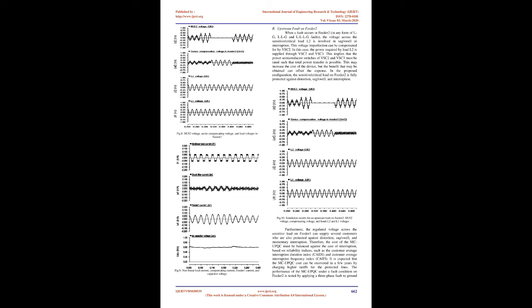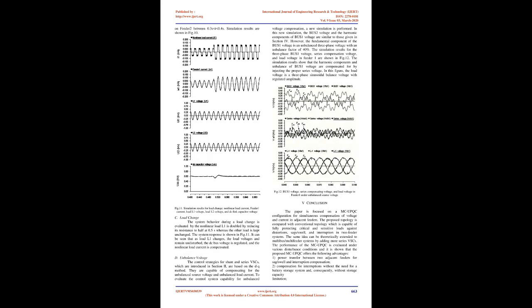Let us consider that the power system in Fig. 2 consists of two 3-phase 3-wire 380 V RMS line-to-line, 50 Hz utilities. The bus 1 voltage, UT1, contains the 7th order harmonic with a value of 22%, and the bus 2 voltage, UT2, contains the 5th order harmonic with a value of 35%. The bus 1 voltage contains 25% sag between 0.1 s and 0.2 s and 20% swell between 0.2 s and 0.3 s. The bus 2 voltage contains 35% sag between 0.15 s and 0.25 s and 30% swell between 0.25 s and 0.35 s.